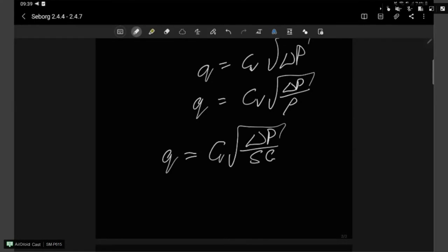It does have dimensions, and it is dependent on a number of things. It doesn't vary too much, but if you need to work accurately, you need to compensate for a change in viscosity, you need to compensate for a change in density. In some instances, you can assume it to be a function of temperature, because viscosity and density will also change with temperature. Don't ever do that for Cv, but just know about the fact that CV is not something that is firm and fixed.